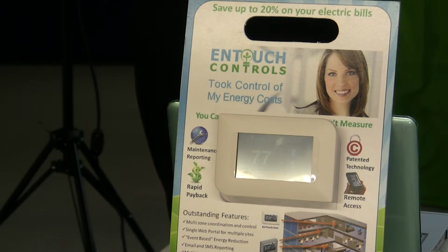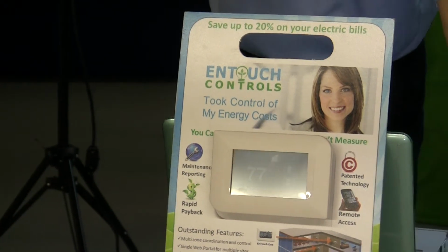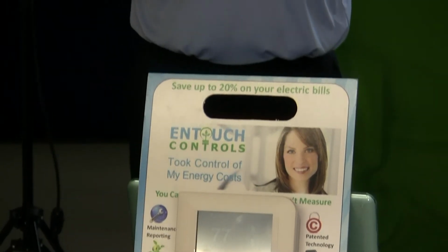That Zigbee radio allows us to communicate to the energy monitor and the lighting control systems, so we're not worrying about being within a Wi-Fi network or how to configure that piece of equipment onto that network. So often the energy monitors and lighting control pieces are stuck in mechanical rooms that have no Wi-Fi network, and they're stuck in metal boxes that are very well grounded. So we have to have a strong enough radio that can get outside that. An answer I can give you on distance, from the controller to the energy monitors and the lighting controls, is anywhere between 250 to 300 feet.